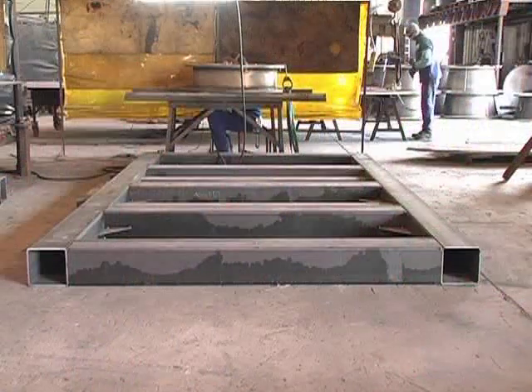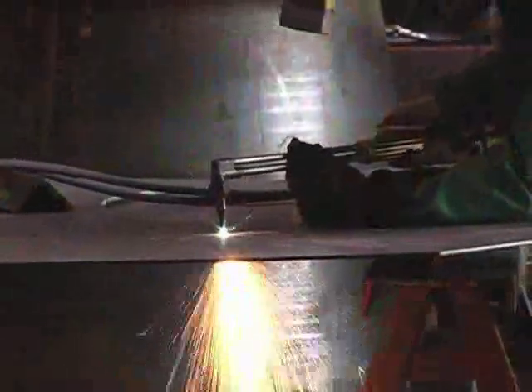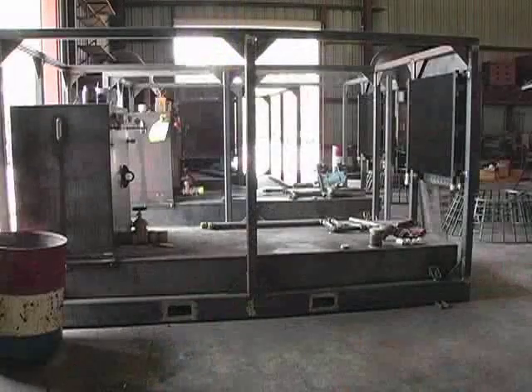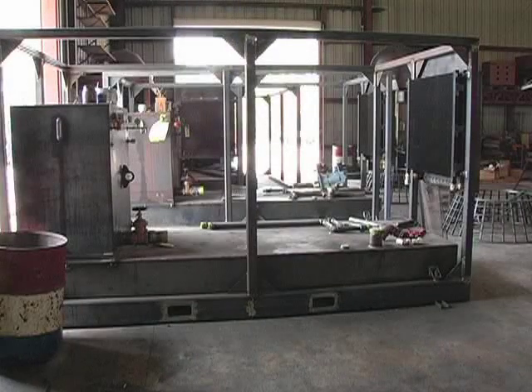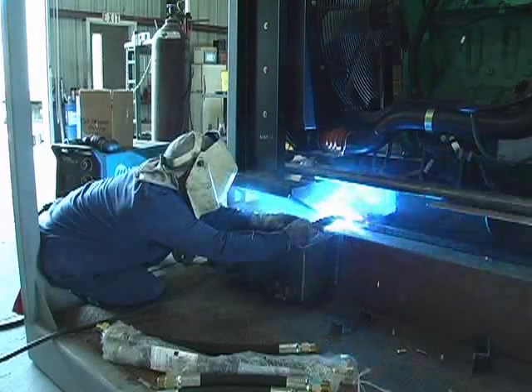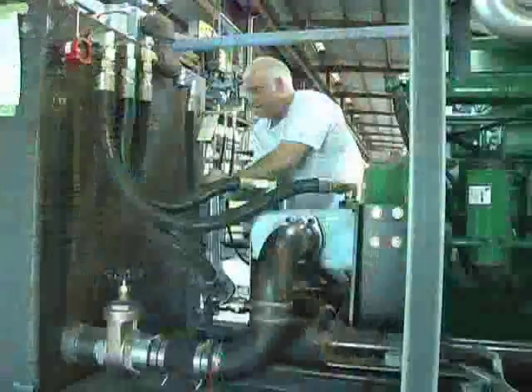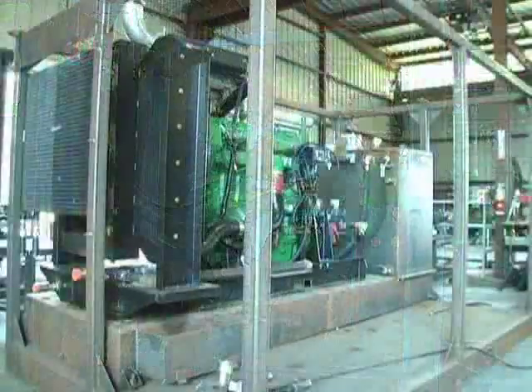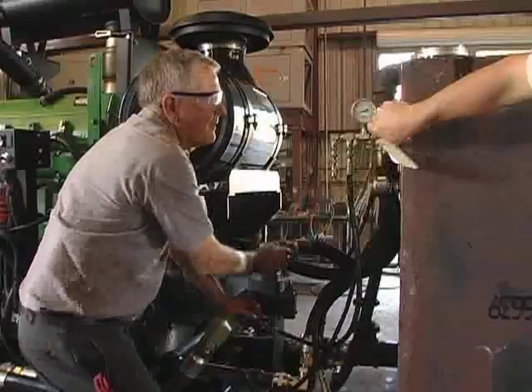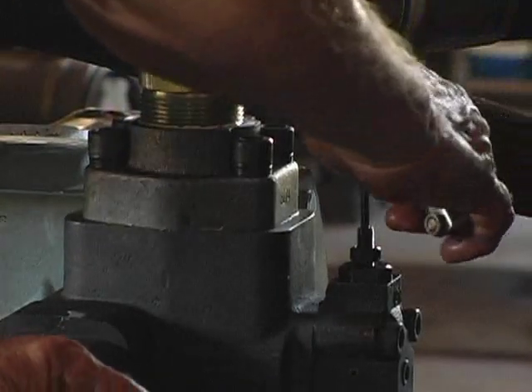The power units are built on a heavy duty rectangular steel base assembled with horizontal and vertical welds. All welders at D&D are certified and experienced professionals. The frame is constructed, then the hydraulic tanks are built and mated to the 500 horsepower John Deere engine. Everything is checked for quality multiple times to assure maximum reliability. Once the skids are assembled with the engines, pumps, tanks, hard piping and coolers in place, the power unit is run dry with no pump attached to set and calibrate all pressures and gauges.